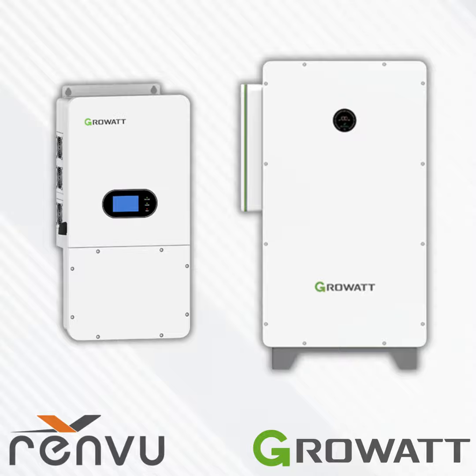You can go to the quick settings, and typically this is also going to be one of the first things you're going to want to do. You go to the network type, and again, you can select Wi-Fi or 4G or LAN configuration. Some of the system settings. Of course, you can power on and off. You can select the grid frequency, the PV input mode. There is a pre-PTO mode as well if you need regulatory approval before you turn the inverter or the battery on and connect it to the grid.